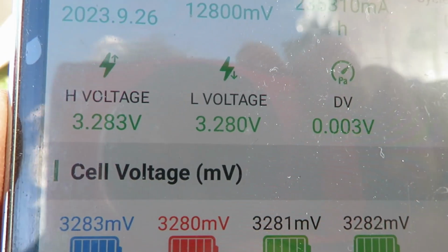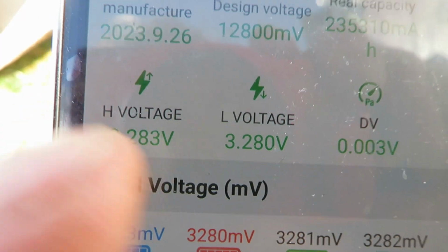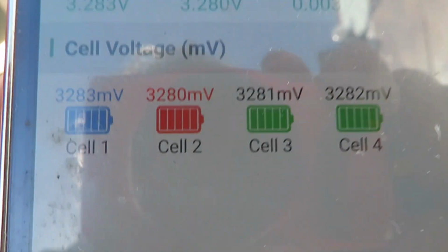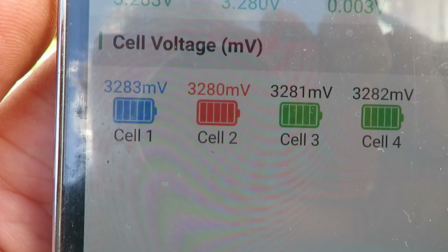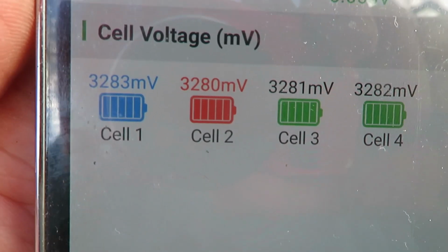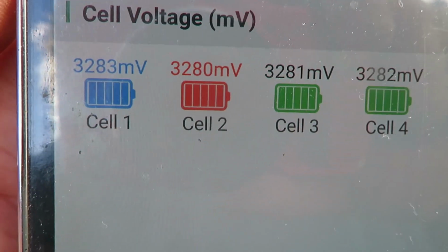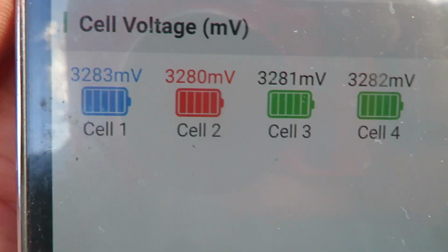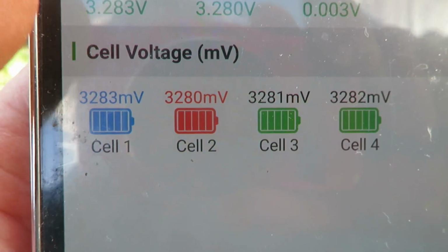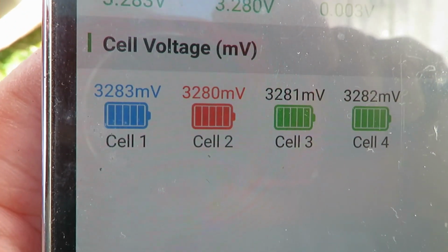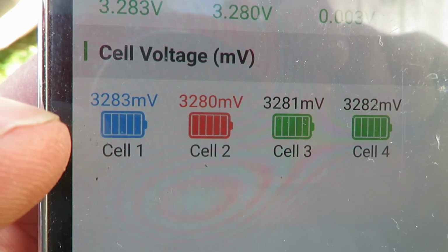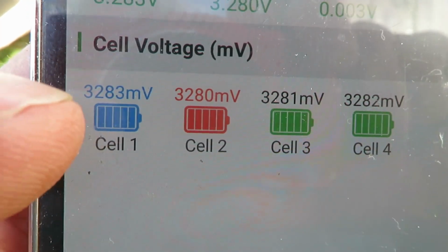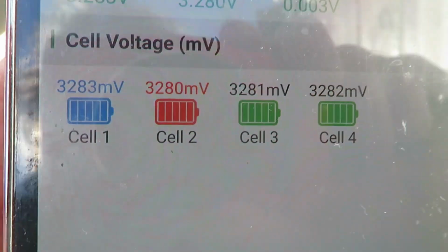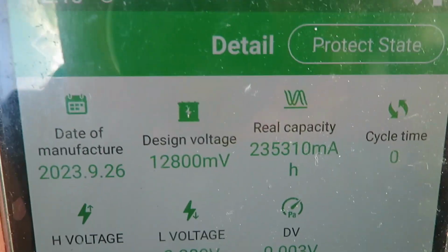No cycle times. It's got the differential between the cells, the low and the high, and here's all the cell voltages. Of course, you won't see any differences until it gets up to its absorb, or the very top charge level, is where you'll see the main differences. You won't see them when they're just sitting idle or being discharged a little bit. They're all going to be close, so you won't see any differential until it's up high in voltage or very low in voltage. That would tell you how well the cells are balanced.